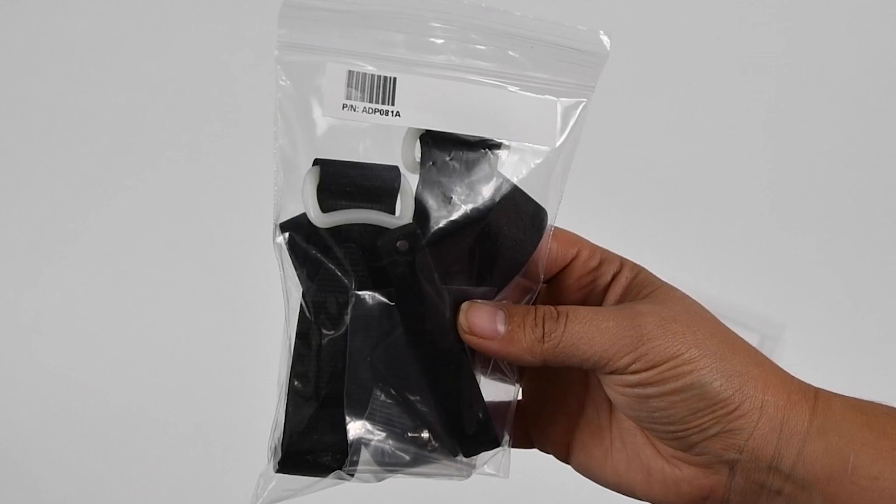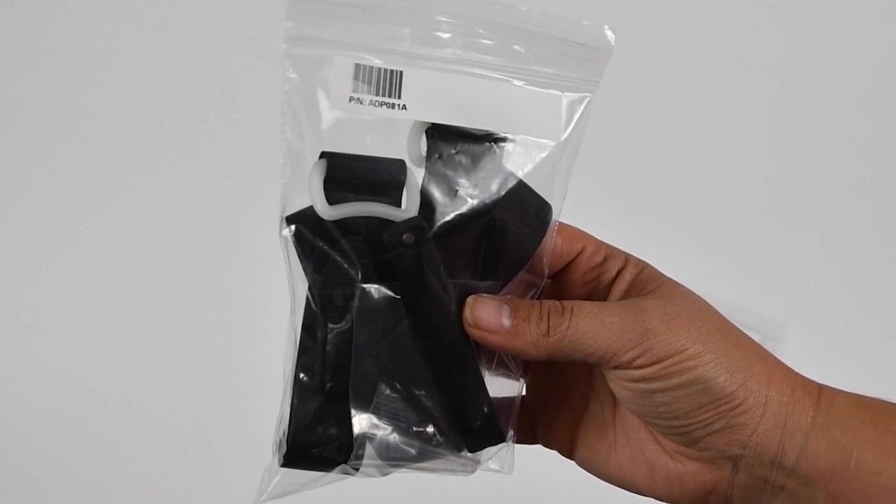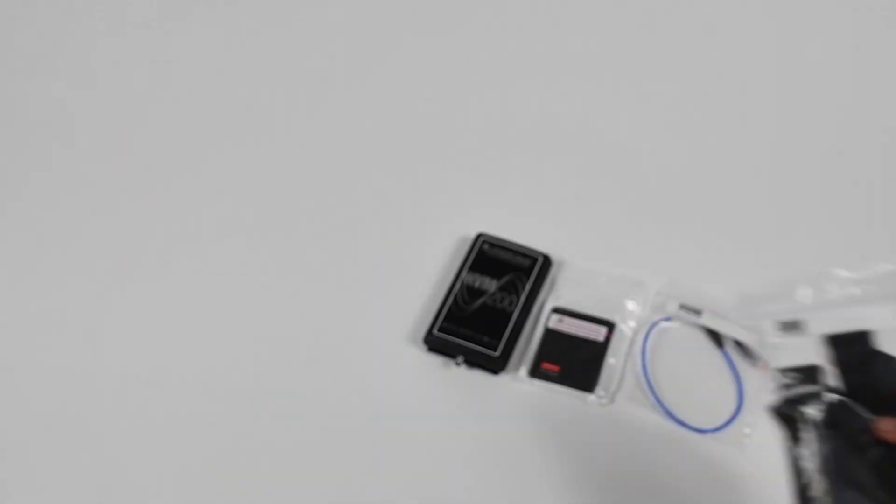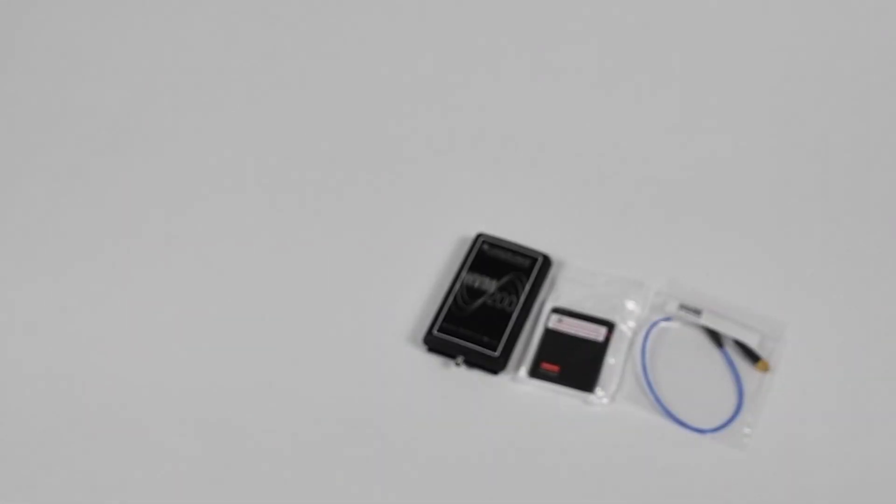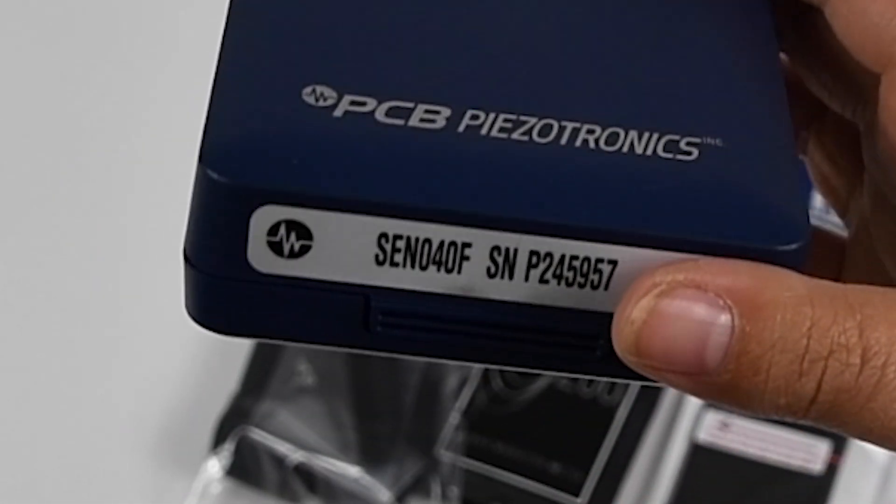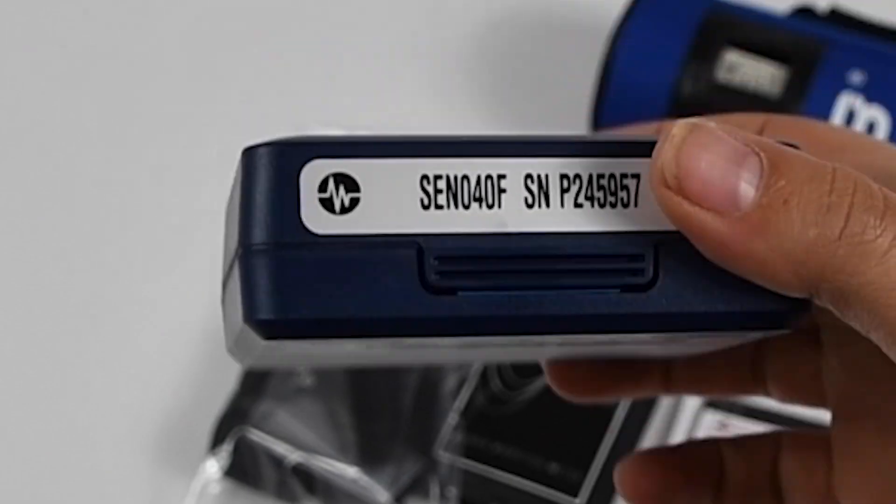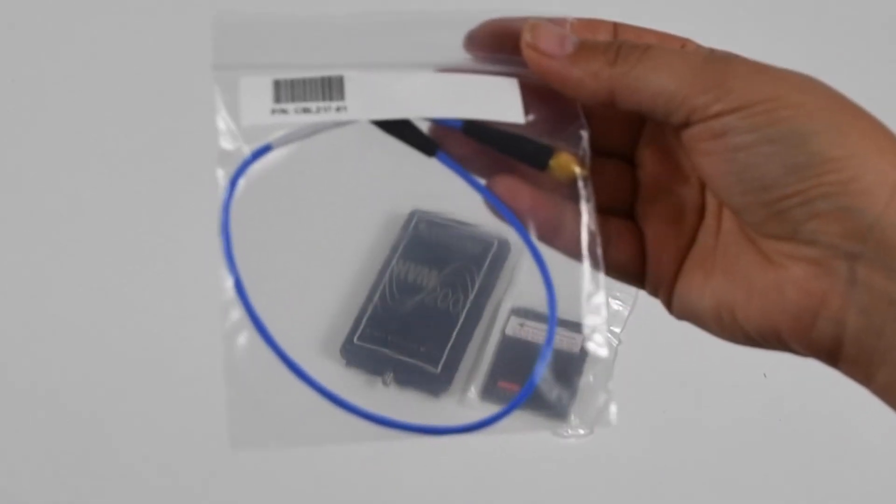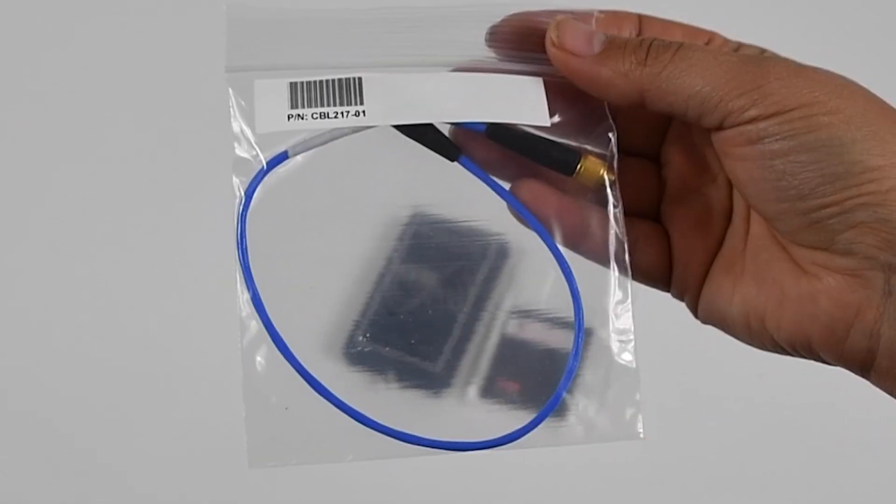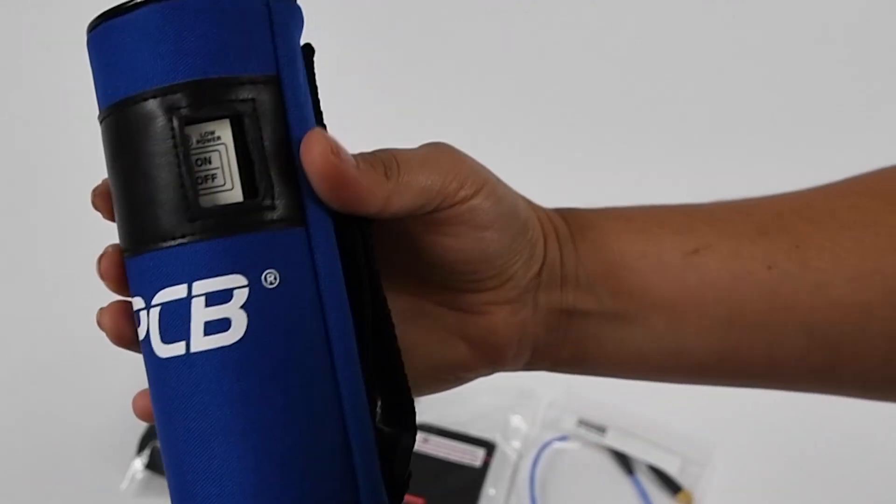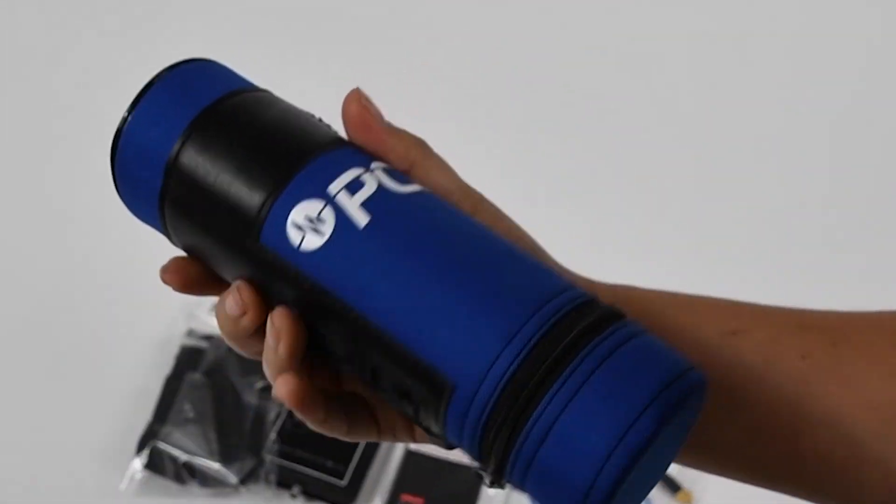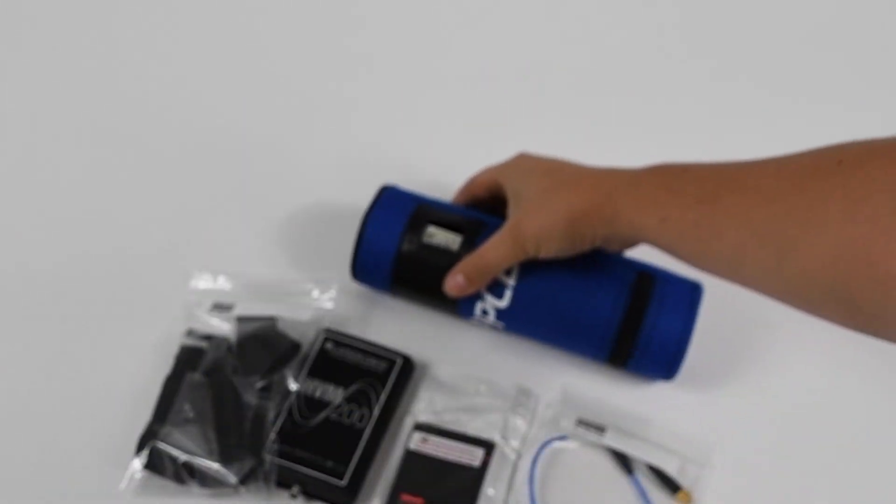In this example, we are going to take a hand-arm measurement using the ADP081A adapter. For this type of adapter, the SEN040F sensor is used. This comes with the necessary cable, CBL217, and we will be testing the calibration with a shaker.